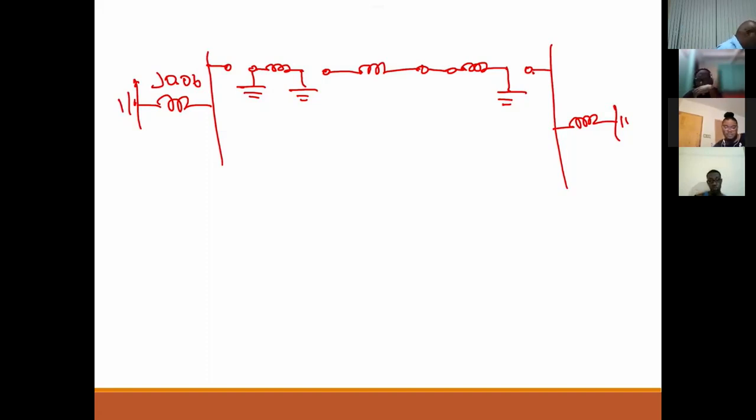All right. So you're going to close A. I mean, I showed you all the A's up top with a circle. So you understand where I'm closing, right? So the reactance there, A is closed. So we include the reactance. But below the transformer, you see that it is earth return impedance. Yes? So because it is earth return impedance, you are going to then put in the 3Zn. And the per unit reactance there is what, 0.03? Yes, sir. All right, so it means now, by the way, I didn't even put in values up top because you're going to see that it really doesn't matter.